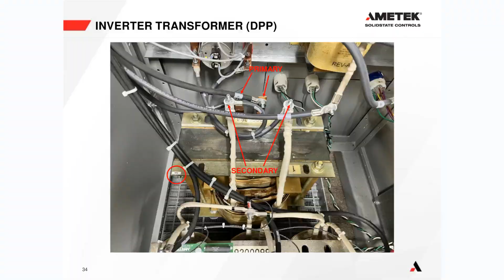I know it's difficult to tell, so I got a better view for you. Once again, our primary is this terminal here and this terminal behind the wire 16 - you can see the copper bus bar it's connected to here. Our secondary is connected to this terminal and this terminal, and the secondary is basically the output of the inverter. It will be 120 volts AC, 60 hertz in North America, a perfect sinusoidal waveform.